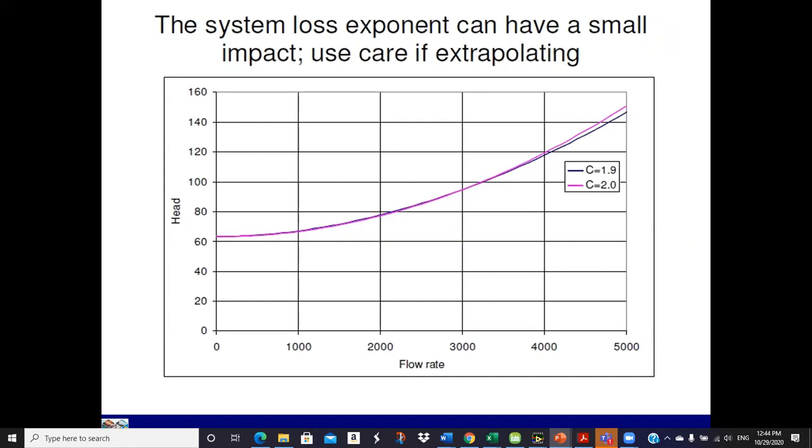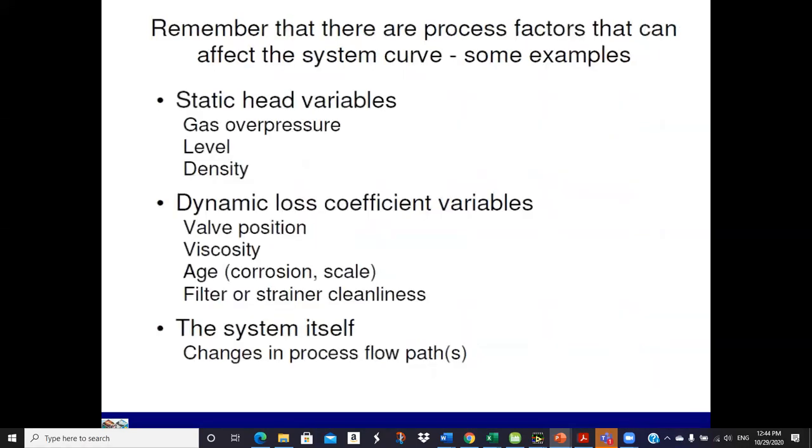All the PSAT and the pumping stuff I have was by Don Cassida. Don had a lot of experience working with data over the years. He came to have the opinion that 1.9 fits real world data better than 2, even though 2 is theoretically what you would use. So you can use whichever you want.